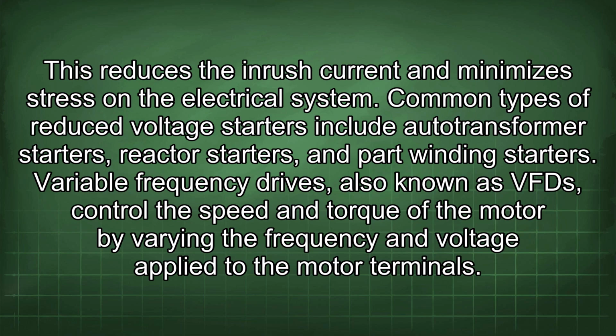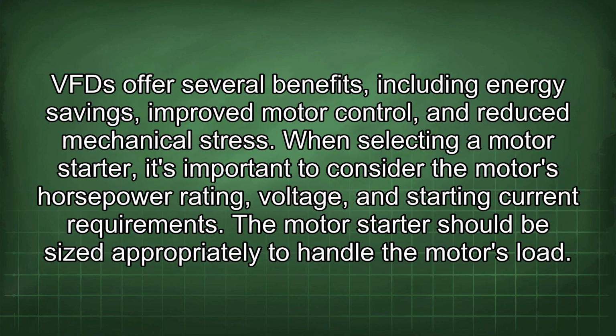Variable frequency drives, also known as VFD, control the speed and torque of the motor by varying the frequency and voltage applied to the motor terminals. VFD offers several benefits, including energy savings, improved motor control, and reduced mechanical stress. When selecting a motor starter, it's important to consider the motor's horsepower rating, voltage, and starting current requirements. The motor starter should be sized appropriately to handle the motor's load.